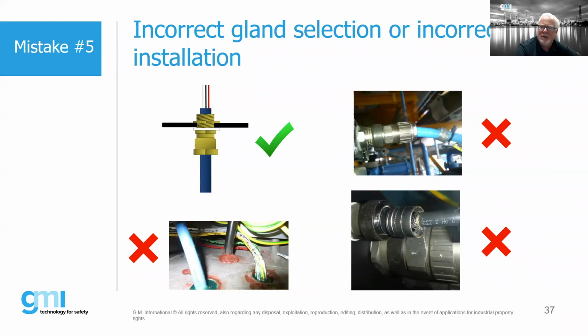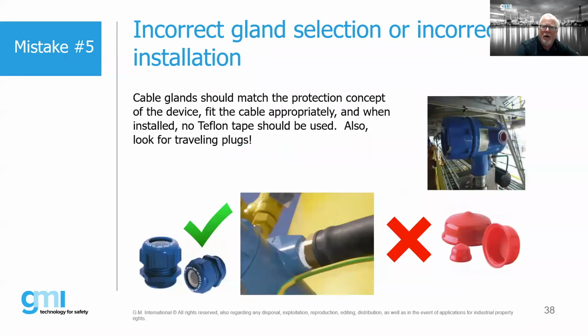And generally our default for many cases around the world is using the gland selection charts in 60079-14. And that information is located in section 9, I believe. So that tells us what types of glands to use, depending on the protection concept. So that's really the important thing that we want to highlight and emphasize on glands.